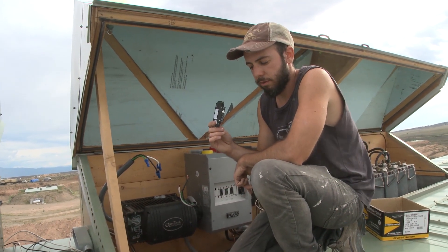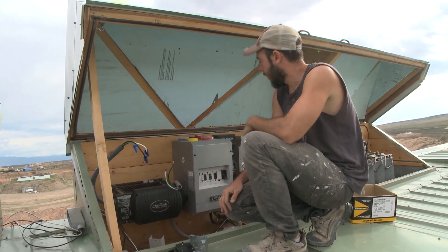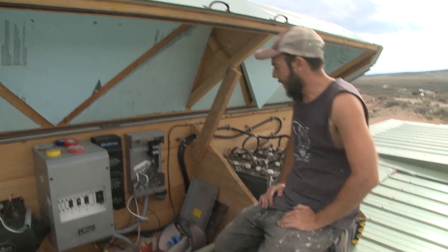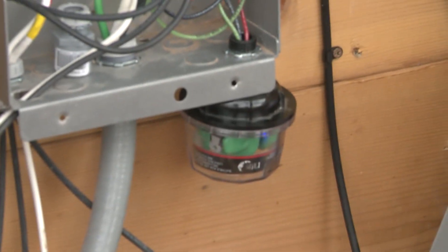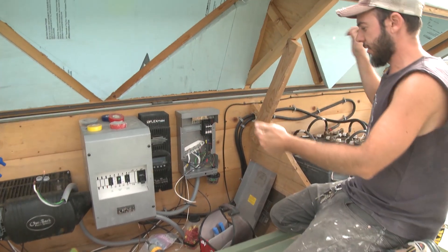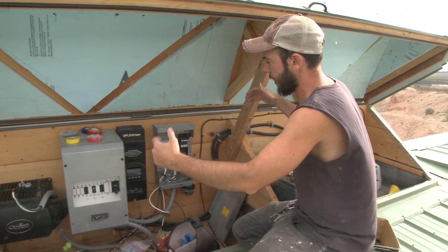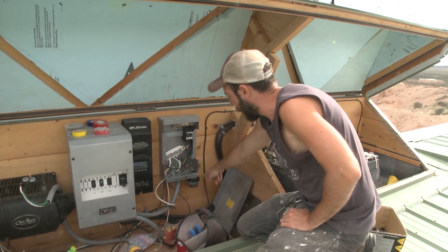That leads me to the next thing I've added: a surge protector. I'm actually using it as a lightning arrester. This is a Midnite Solar lightning arrester and surge protector. You connect it at the combiner box where the solar panels come in, protecting against a lightning strike on the panels and the surge of power coming in through the panels into the combiner box breakers.